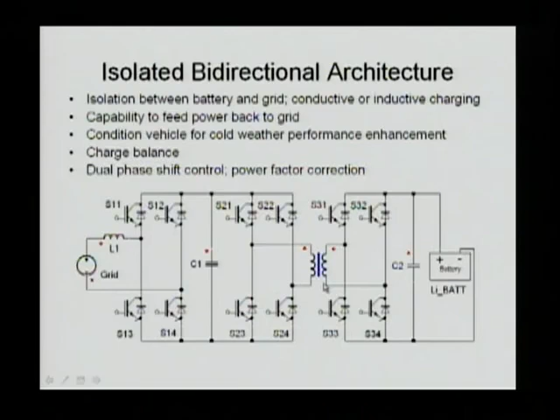The isolation is done through the isolation transformer. Because it's a high frequency transformer, the size is quite small. At the same time, because the isolation transformer can be designed this way, we can actually do inductive charging, meaning there's no electrical contact between grid and battery. All you have is an isolation transformer designed as an inductive charger.